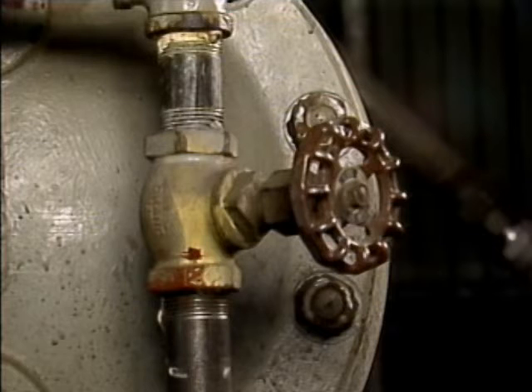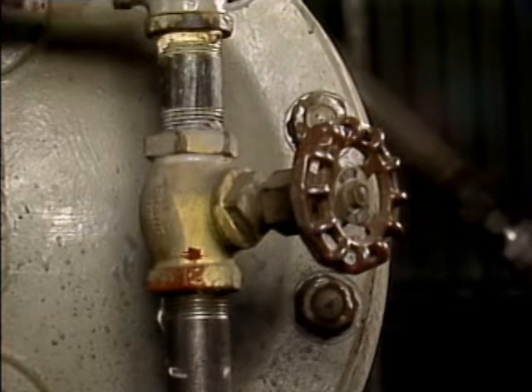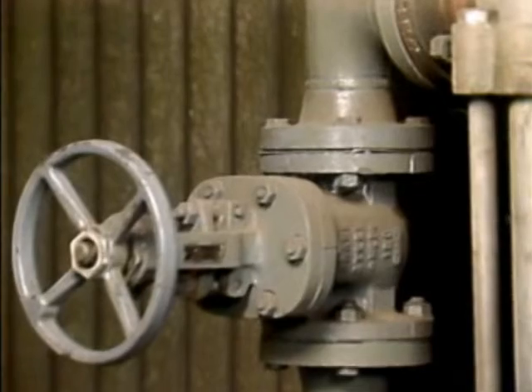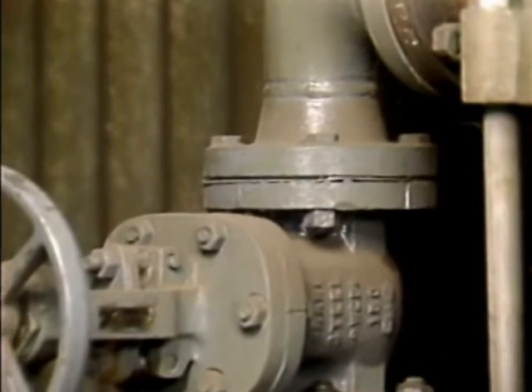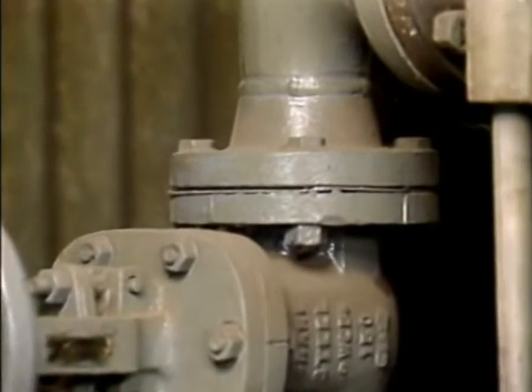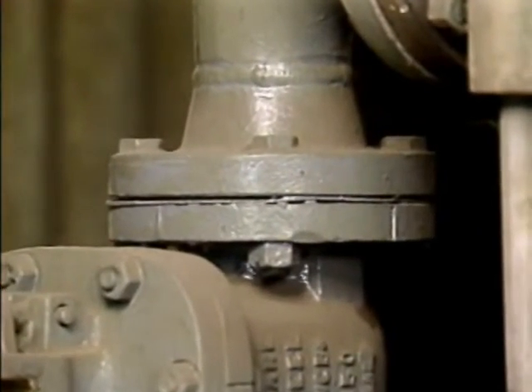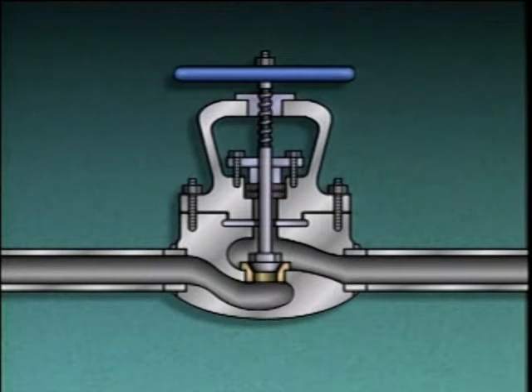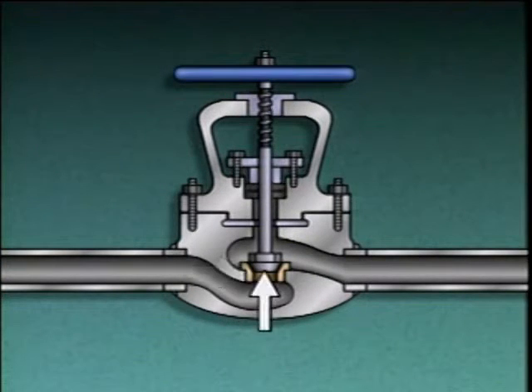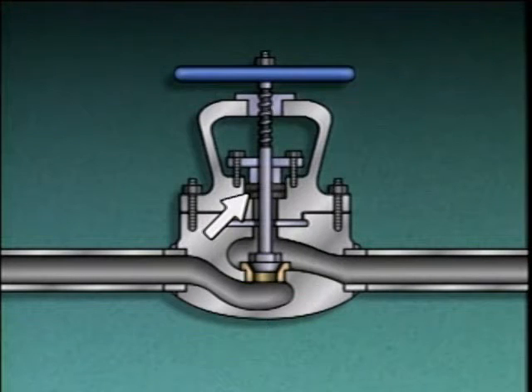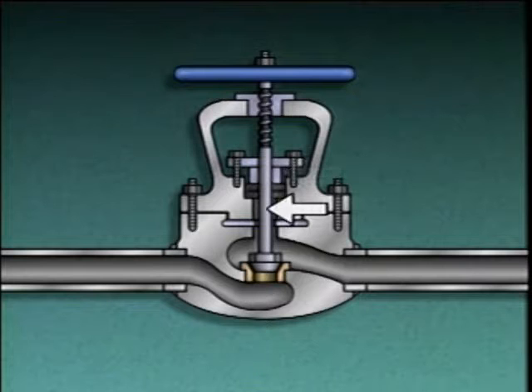Threaded connections are generally used on small valves in low-pressure systems. Flanged connections are commonly used where operating conditions may require frequent valve replacement or repair. Other parts of a valve may include a seating area or seat, a disc, a bonnet, packing material, a packing gland, and a stem with a hand wheel attached to it.